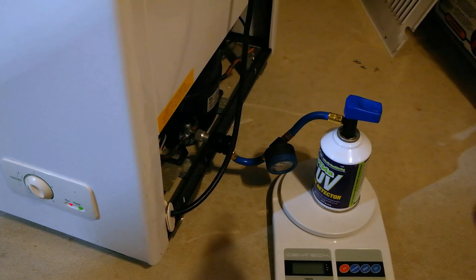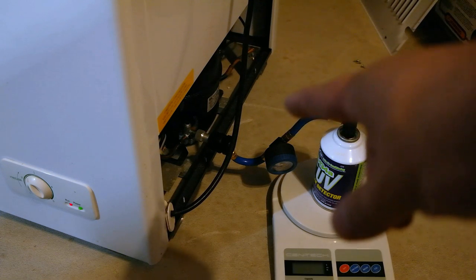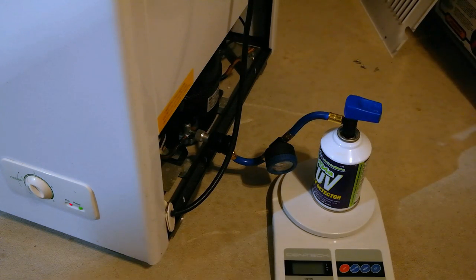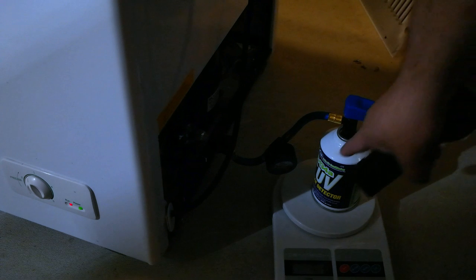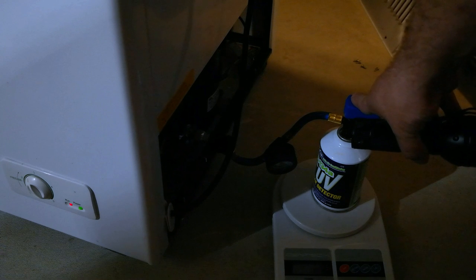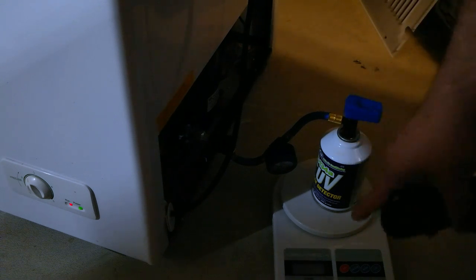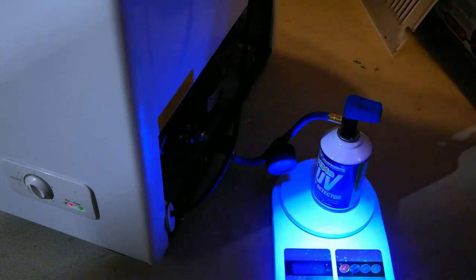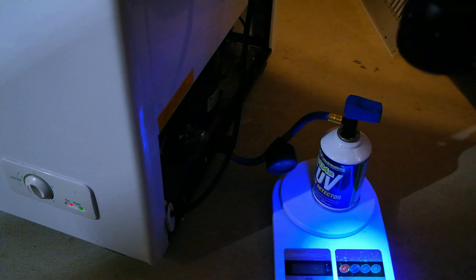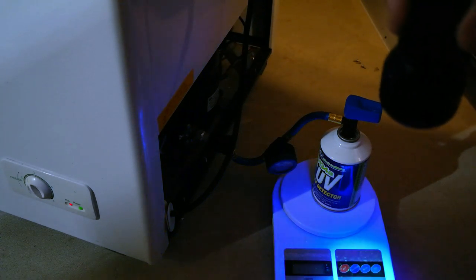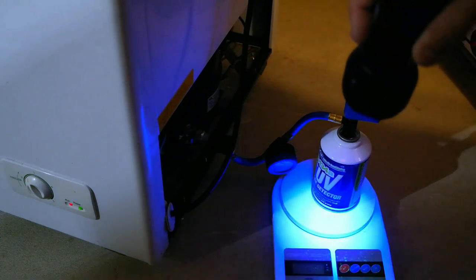The other side of the coin is where did that old Freon go? This is why we used Freon with UV in it. And just to show how the UV works, I had a previous one of these that was about three years old and it spilled on me and went all over the place. So I have it on my scale right now. And you can see all the nice little green splatter down there. Yeah, that's the UV dye.